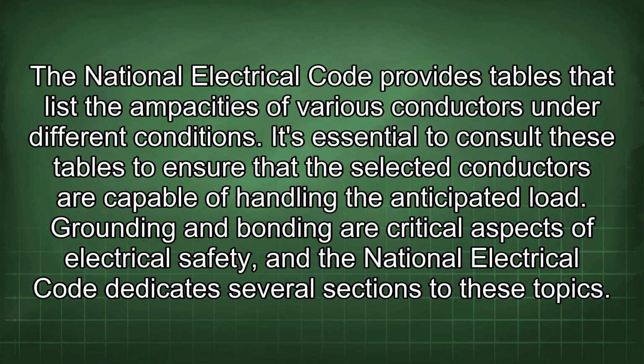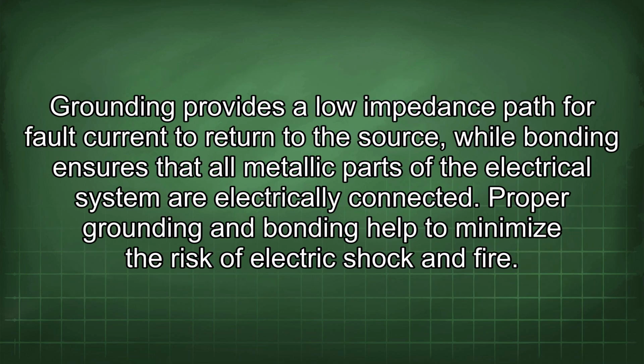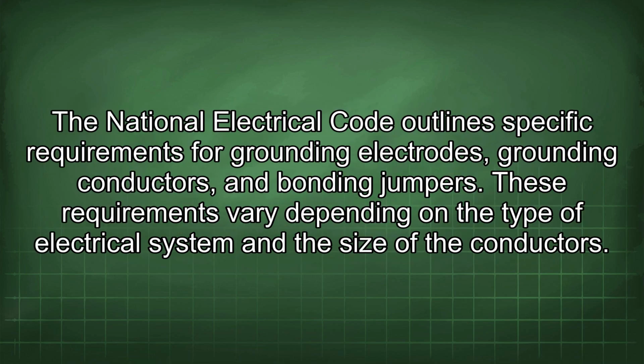Grounding and bonding are critical aspects of electrical safety, and the National Electrical Code dedicates several sections to these topics. Grounding provides a low impedance path for fault current to return to the source, while bonding ensures that all metallic parts of the electrical system are electrically connected. Proper grounding and bonding help to minimize the risk of electric shock and fire. The National Electrical Code outlines specific requirements for grounding electrodes, grounding conductors, and bonding jumpers. These requirements vary depending on the type of electrical system and the size of the conductors.